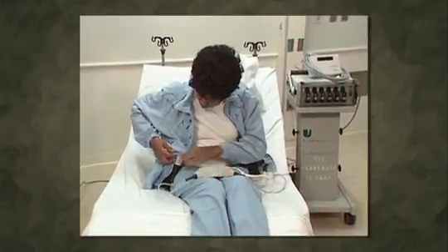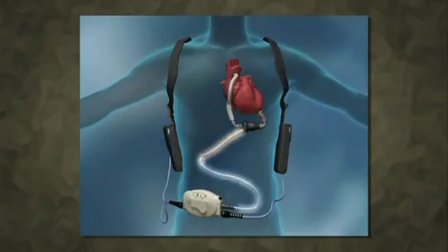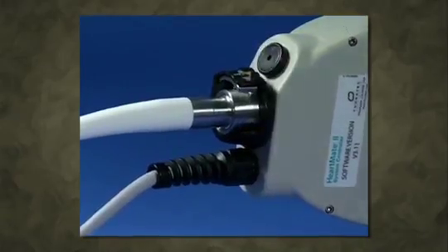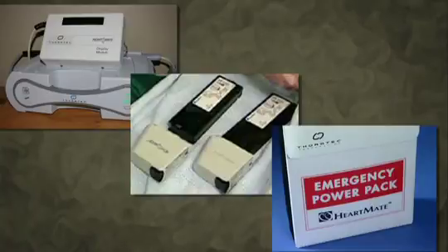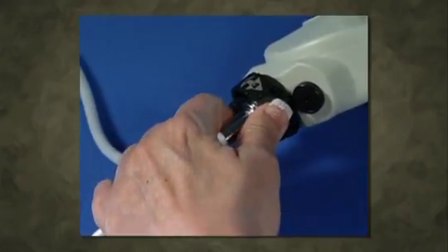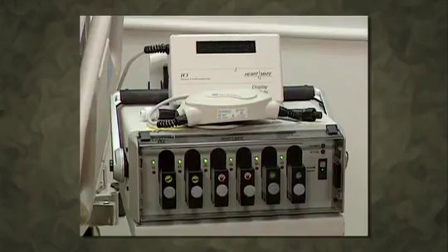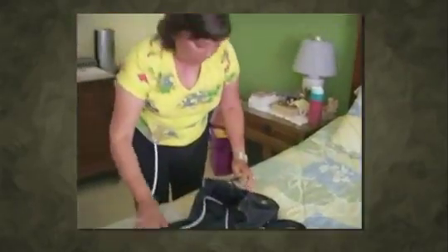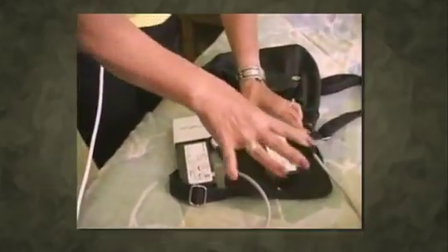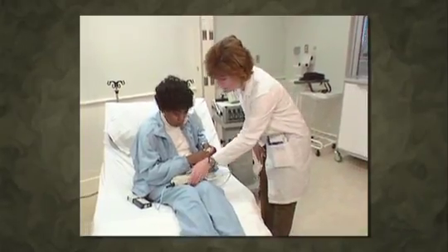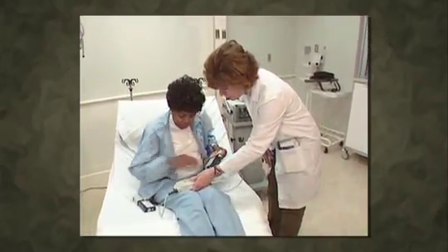Prior to your arrival, they should have checked to see that the percutaneous lead was attached correctly to the system controller and that the controller was properly connected to a functional power source, such as the power module, batteries, or emergency power pack. They may also have replaced the system controller with a backup that they keep with them. Find out what they have done and ask them to show you the connections. This step helps to confirm that everything is hooked up and may also help them to double-check any of the adjustments they have made. Also, you should be able to converse with one of the LVAD coordinators from the hospital.